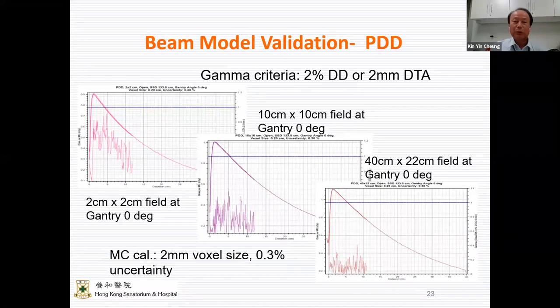Now these are typical beam validations that we went through. On the left is the 2x2 field percentage depth dose, superimposing the computer calculated depth dose and our beam data measured using the water tank. The criteria for acceptance is 2% dose difference and 2 millimeter distance to agreement, and they fall well within this criteria. And for the 10x10 field, for example, and the 40x22 cm field, they look pretty good.